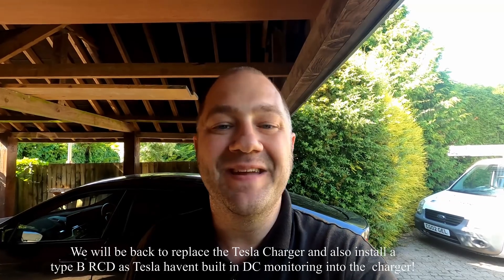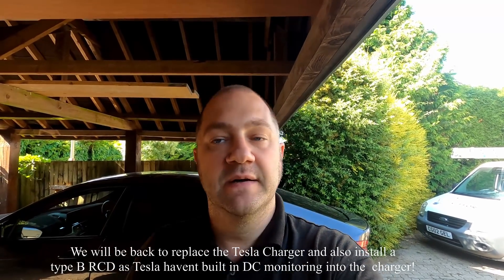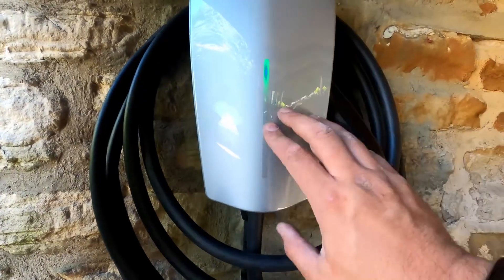This job is done and dusted. Sadly the Tesla unit appears to be faulty - I plugged it into the EV tester and just get a solid red light on the Tesla charger. According to the manufacturer's instructions that means there's a hardware fault with the unit. It is powered on and we know the circuit tests are all good - it's just a shame the unit won't do anything. We tried to reset it and nothing works. Please remember to like and subscribe using the big red button below, click the bell for notifications, and I'll catch you again soon.